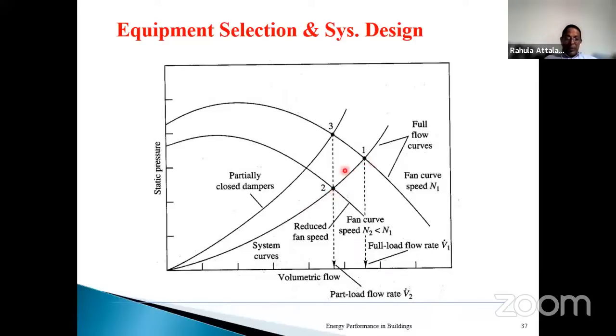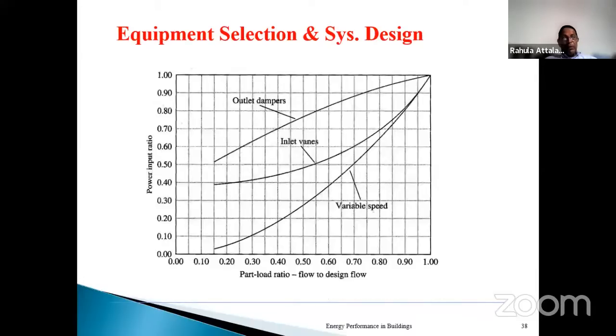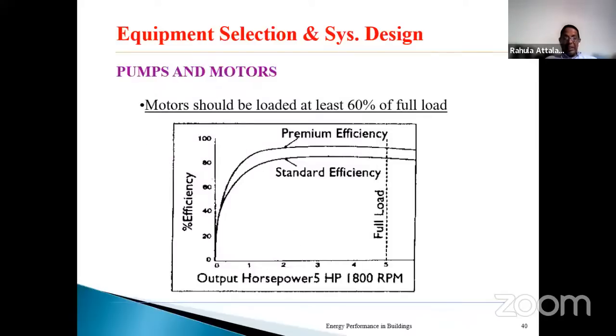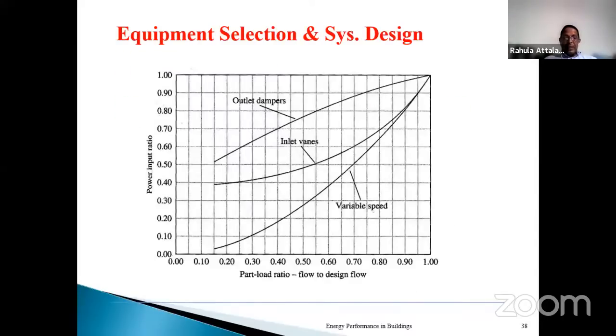By doing that, you can save this amount of energy. If you had used the valve to reduce the flow rate, this amount of energy would be lost. That's the basis behind the variable speed drive for changing the flow rate, because when you change the load, you need to change the flow rate of chilled water, and also sometimes condenser water as well. This will indicate how the power input changes depending on whether you are using a variable speed drive or closing the discharge valve. You will see that the power drop from here to the lower value is much higher with a variable speed drive than with outlet damper or discharge valve control.